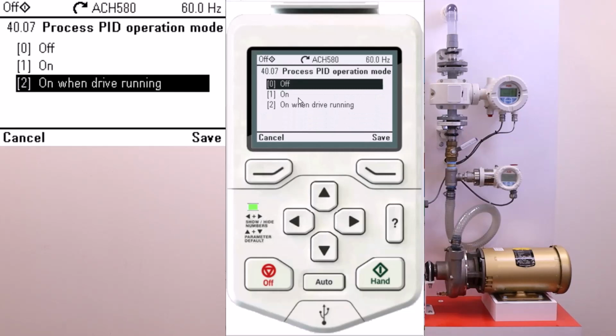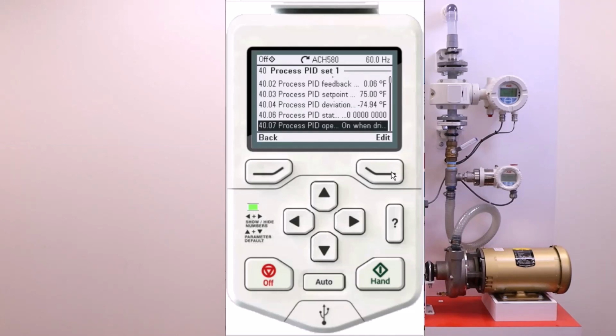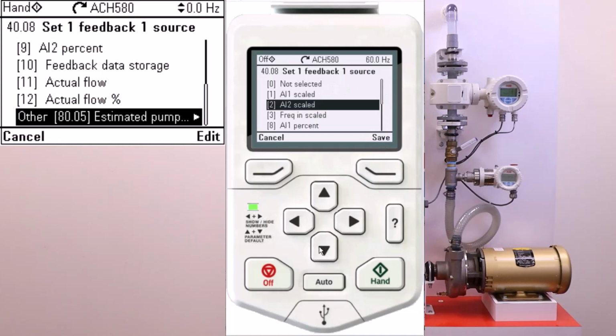We can just go it's on all the time, or we can go when it's on when running. In this case, we'll put it on whenever the drive is running. So whenever the drive is running, the PID loop is on. We need to know what the PID loop needs to look at in order for it to operate. So let's just go down to the next parameter, which is 40.08. And that's your feedback source. Right now it's analog input 1 scaled. We don't want that.